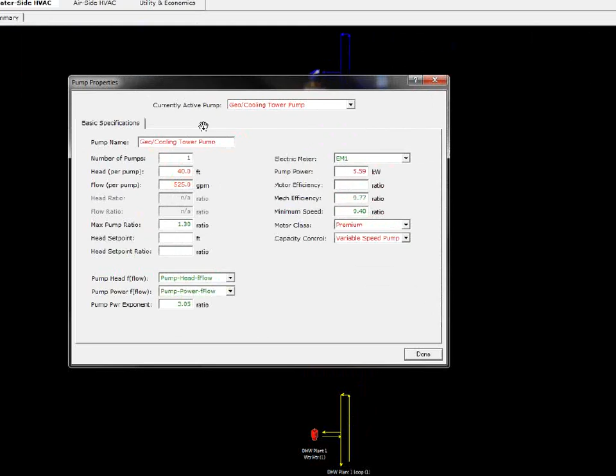Now I had to account for the pump energy on both the cooling tower and the geothermal pump. There's a pump out on site that pumps the geothermal water. This one took some thinking, or hoping, I guess. I got lucky. Both pumps were the same size, 7.5 horsepower, and I figured one or the other is going to be available at all times. If it's heating, the geothermal pump's going to be running in the wintertime, and in the summertime the cooling is going to be available.